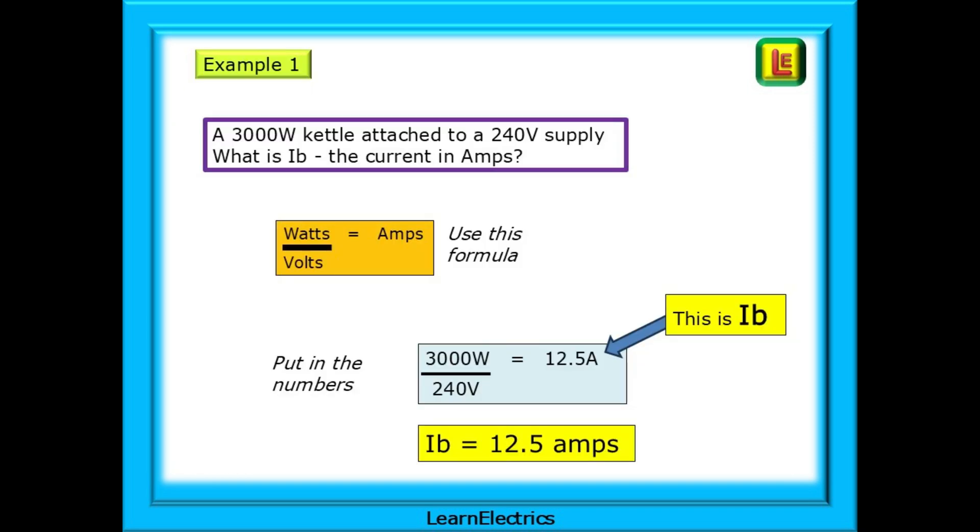Let's do an example calculation. We are asked, a 3000 watt kettle is attached to a 240 volt supply. What is IB, the current, in amps? Use the formula shown and put in the numbers given in the question. 3000 watts divided by 240 volts is 12.5 amps. That is our answer. IB, the design current, is 12.5 amps.